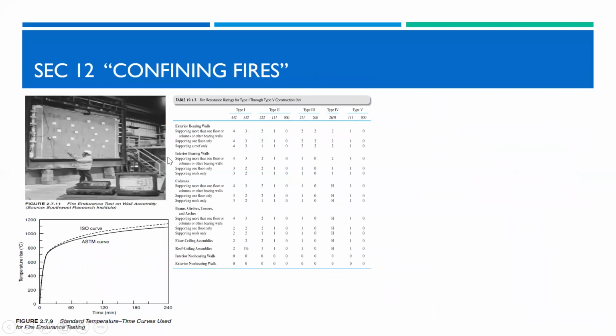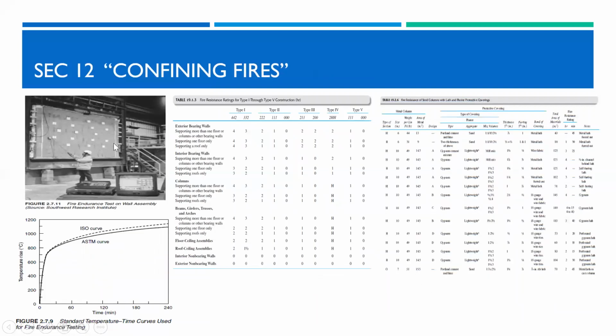Confining fires: here we are testing the firewall. If you are using a fire rated wall, we have to use the ASTM curve, the ISO curve, and we measure the exposed temperature of the other side to know if the sample test is passed or failed. And here we have types of construction 1, 2, 3, 4, 5 with bearing wall, interior wall, column, roof, and floor. We have fire door rating based on the wall rating.